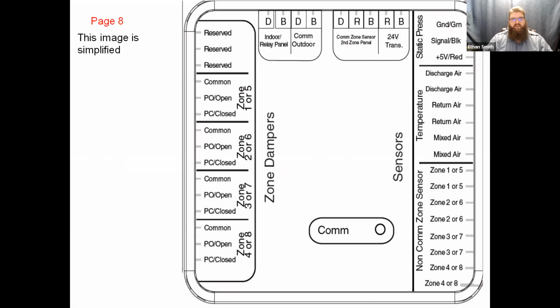The requirement for this zoning system, though, is that we do have to be able to talk to the blower motor directly. So when you apply this to a relay panel, you also have to make sure that your indoor equipment is a Trane or American Standard indoor piece of equipment with a variable speed blower only. Okay, no PSC blowers, no X13 motors. It's got to be a variable speed blower. The way that you can tell that is if your furnace has a BK terminal on it or your air handler has a BK wire in it, you can use the zoning system. But it's got to be Trane or American Standard variable speed blower.